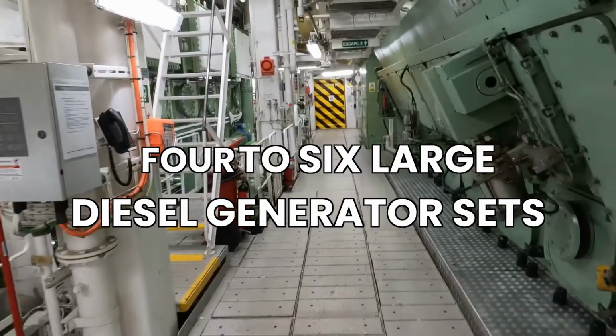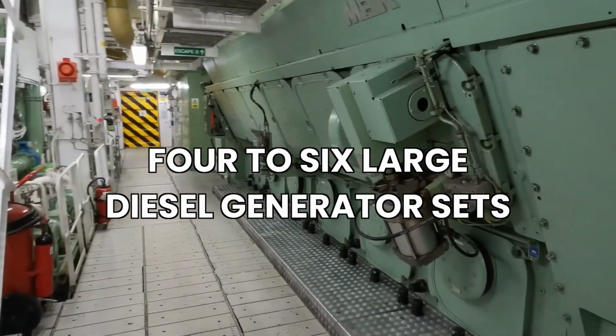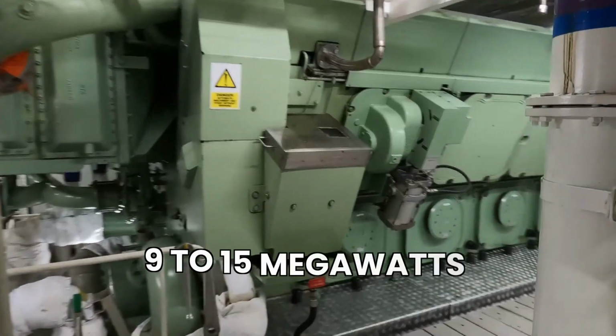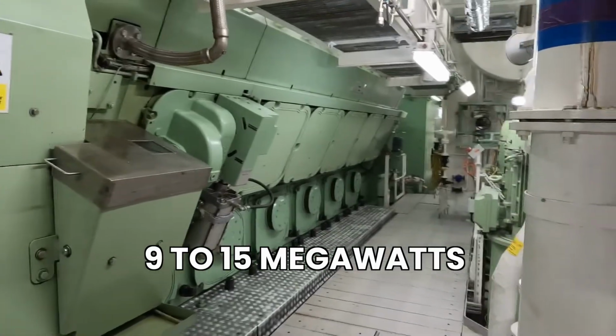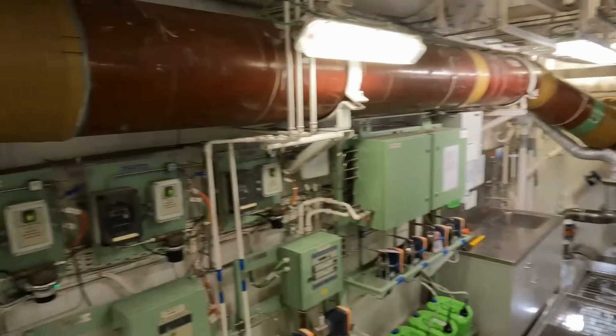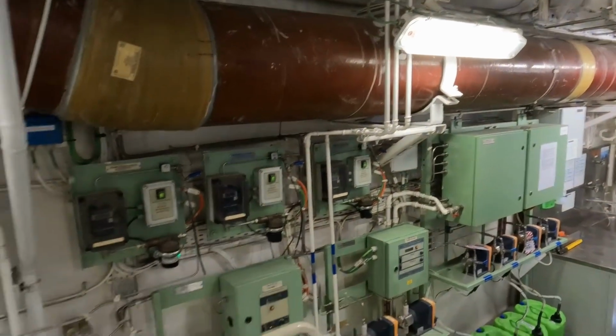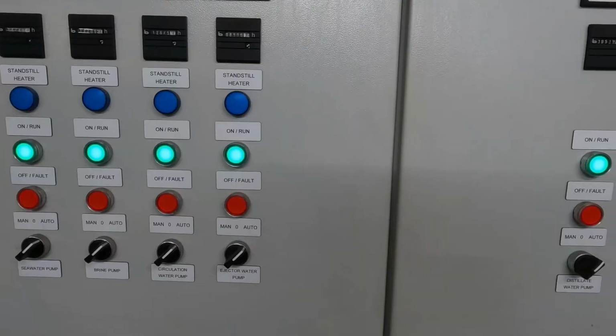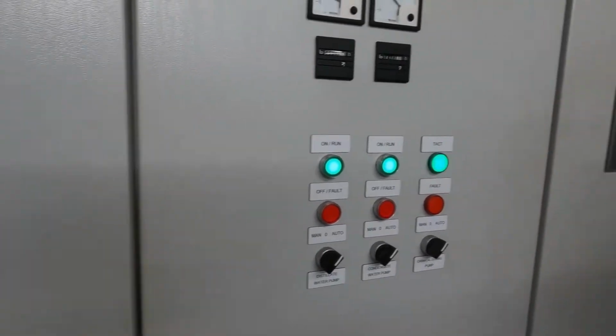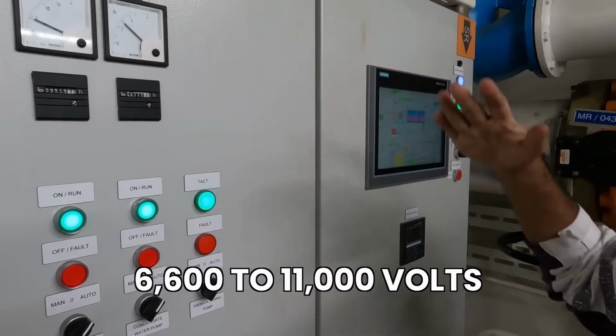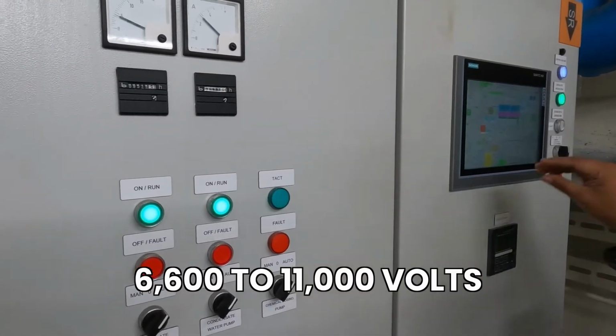Below decks, the ship runs 4, 5, or 6 large diesel generator sets. Each one produces between 9 and 15 megawatts of electrical power. They are not driving anything mechanically. They are feeding electricity into the ship's main high-voltage switchboard, typically running at 6,600 to 11,000 volts.